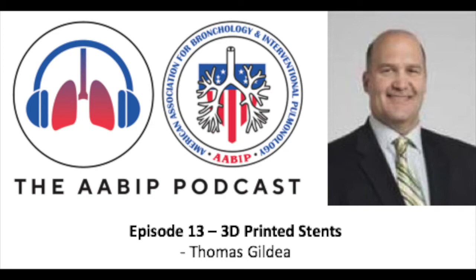Regarding the technical aspects and management, I presume the loading, deploying, and maintenance are much like any other silicone stent? Right now, we've designed them exclusively to work with the existing rigid bronchoscope systems. We used the Bryan-Dumon system as our model — our packaging really speaks to it fitting into the standard set with the Bryan-Dumon loading set. We could put some things that are a little larger in, but we haven't validated that outside with the Storz equipment, for example, or things like larger Y stents that you can place without a load system. But existing loading systems.